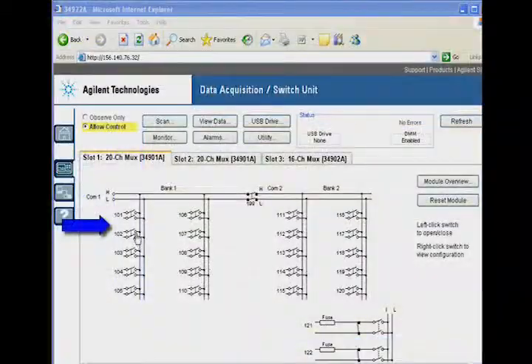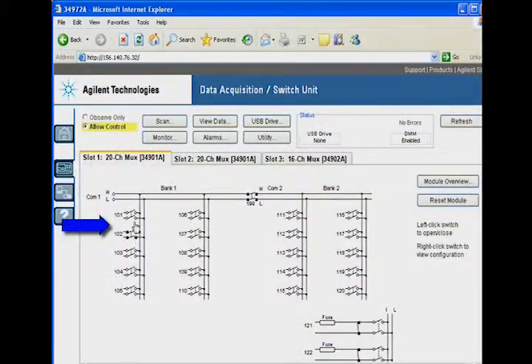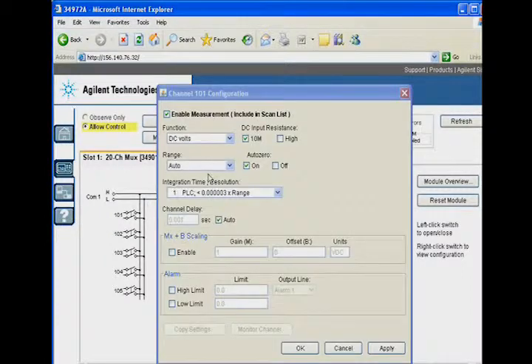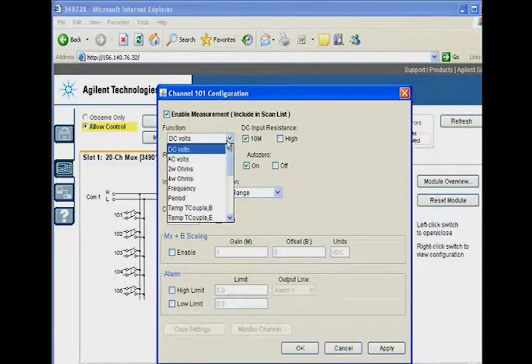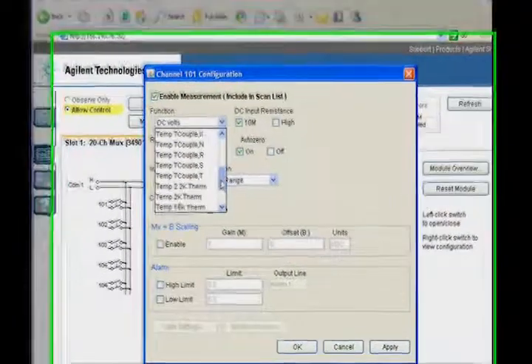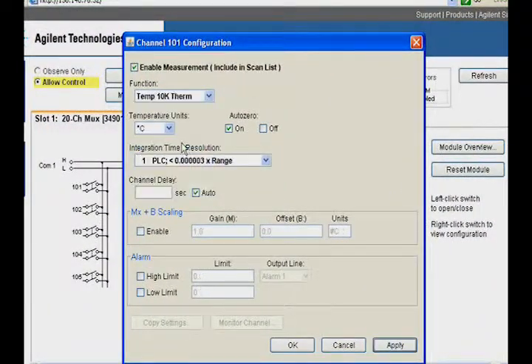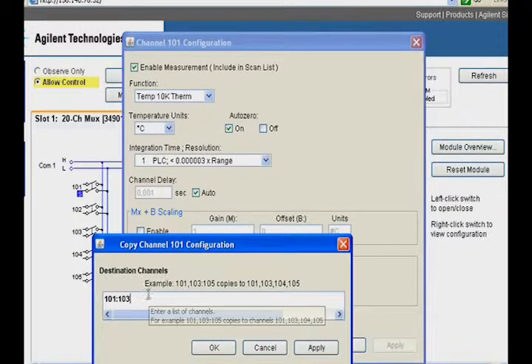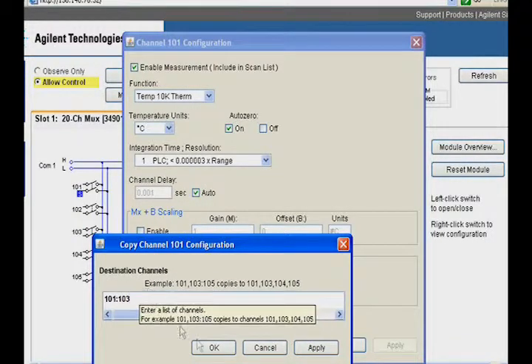You can view and control the switch settings and set up each channel for measurements. Select AC or DC volts or current, resistance, frequency or period. Or you can measure temperature using different transducers. Select the integration time, and now you can copy the setup to multiple channels.